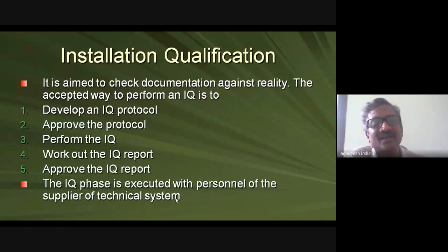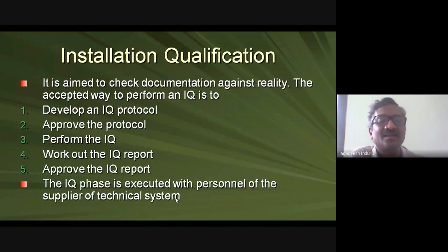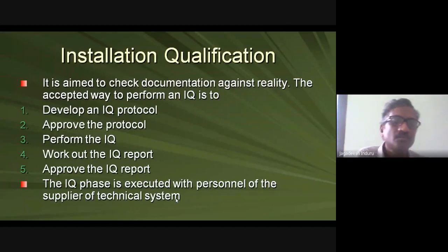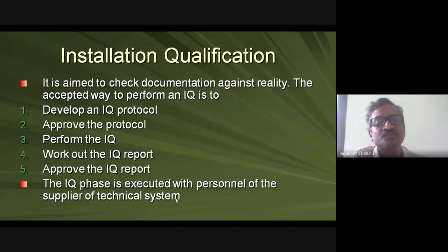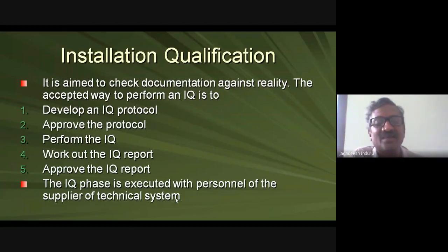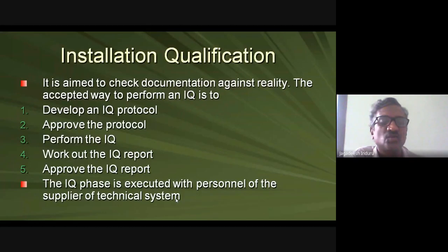The IQ phase is executed primarily by the supplier's personnel — the vendor opens the package, removes all items, explains and demonstrates them, and confirms everything matches. The factory personnel's intervention is minimal. If it matches you proceed with installation; if not, you reject and return it, informing them you will not pay because the supply did not meet your requirements.